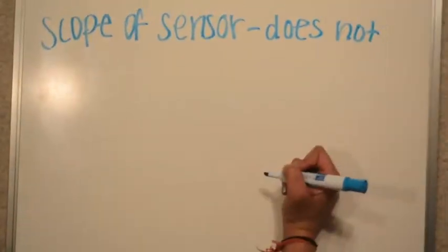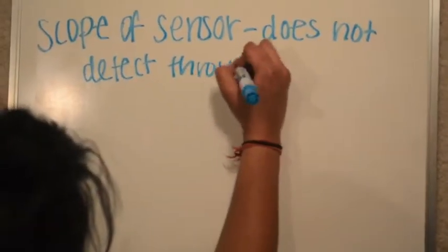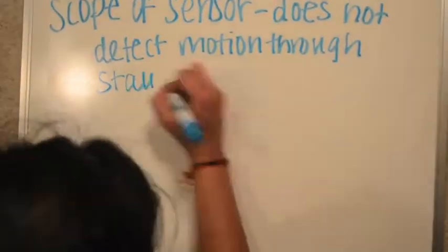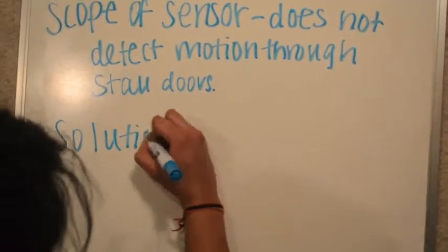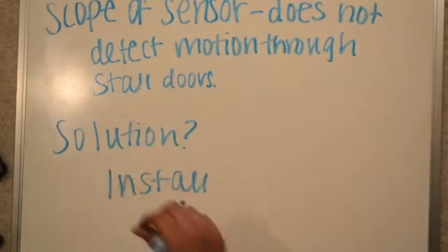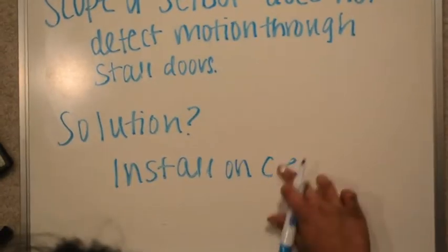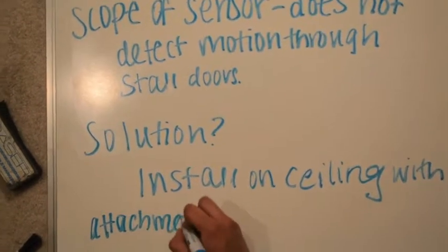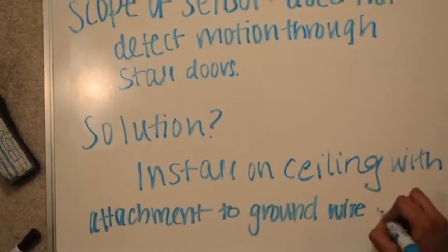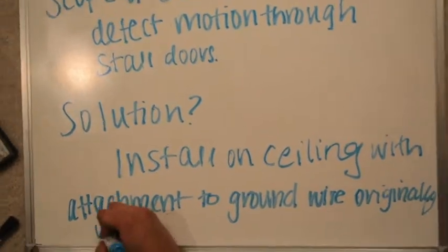Because our automated sensor uses passive infrared to detect motion, it can be blocked by stall doors and walls in the bathroom. So when we mount our automated sensor, it should be mounted on the ceiling above the stall so it can sense motion through the gaps above the stall doors. The panels that make up the ceiling of the bathroom are removable, so installing the automated sensor should be as simple as connecting it directly to the main wire that feeds electricity to the lights in the bathroom, thus allowing it to control when the lights turn on and off.